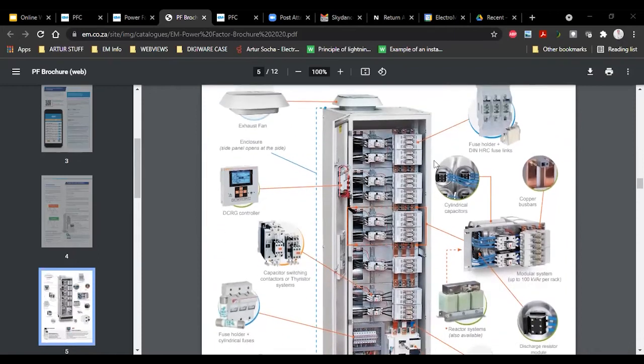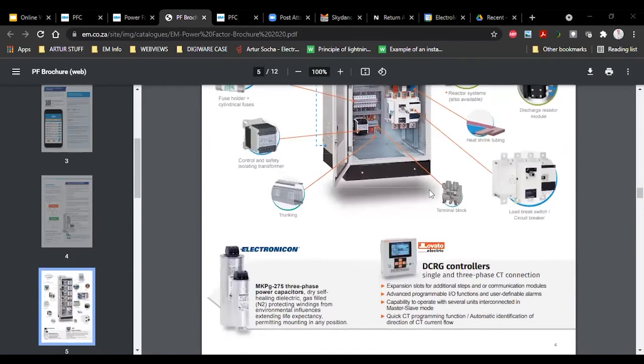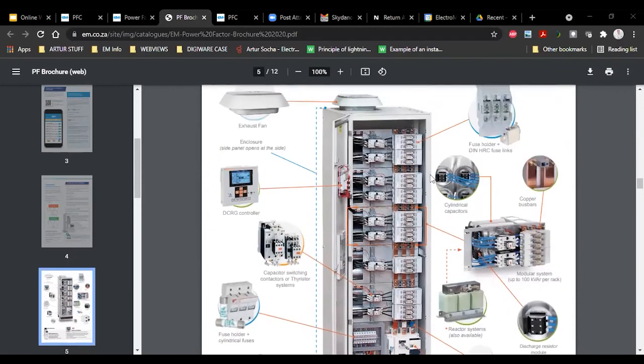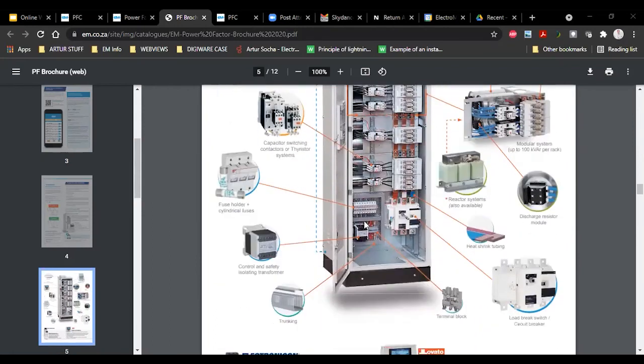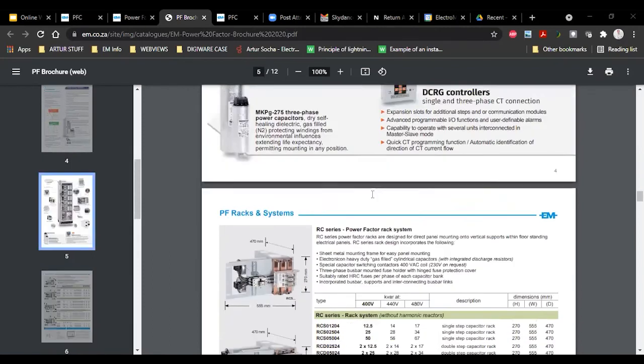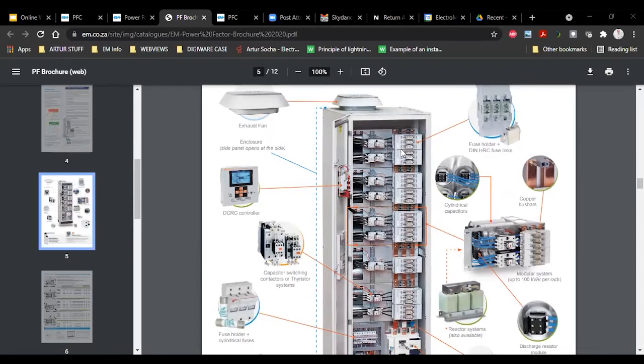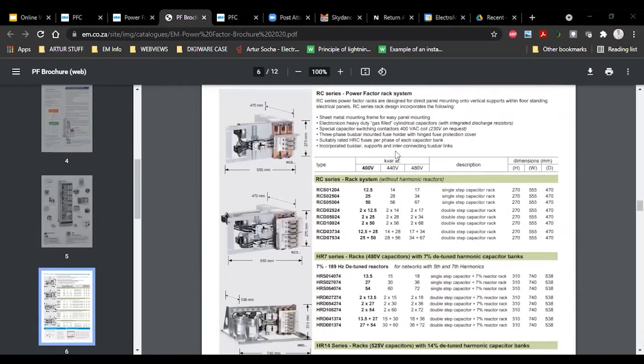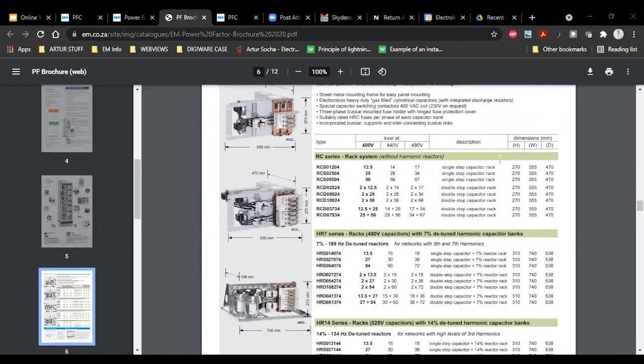This is a typical floor standing non-reactor unit, showing you all the components that are used within this. Serviceable components: any one of these racks could be removed and replaced with another. Contactors can obviously be replaced, fuses and so forth. These floor standing units are physically assembled here in our Sandton branch by our workshop. Customers could buy complete systems, of pretty much any size, or customers would just buy the racks from us. So we do racks that are non-reactor. You'll see they're a little bit smaller. That's just fuse holder, contactor, cap.